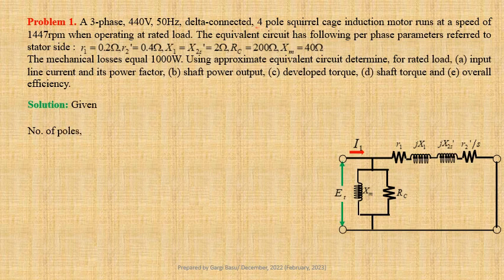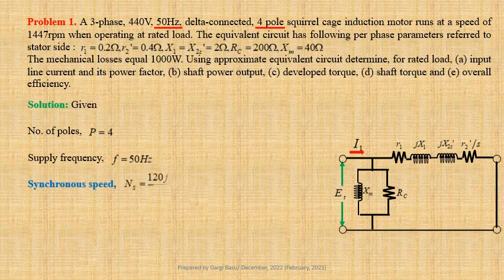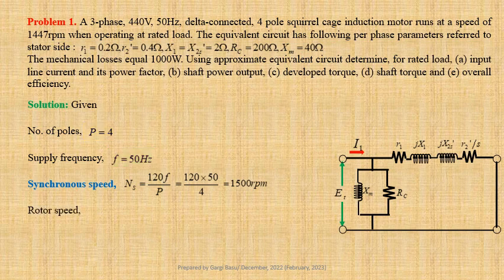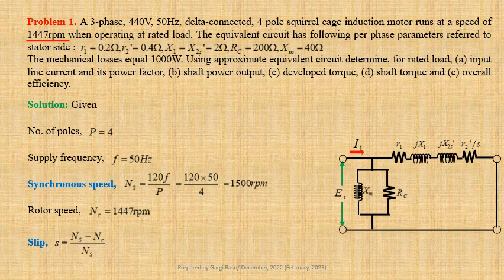Number of poles of the machine P = 4, and supply frequency F = 50 Hz. Let us now calculate synchronous speed: Ns = 120F / P = 120 × 50 / 4 = 1500 RPM. Given rotor speed Nr = 1447 RPM. Now we shall determine slip: S = (Ns − Nr) / Ns = (1500 − 1447) / 1500 = 0.03533 per unit.